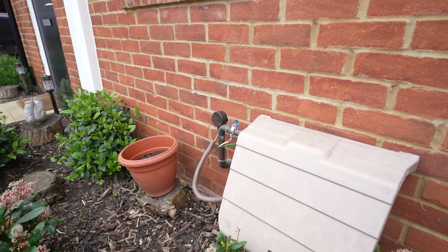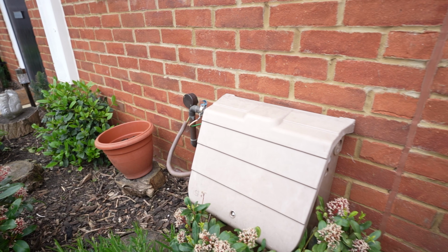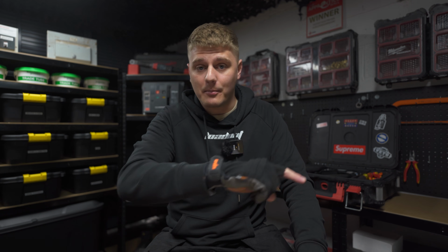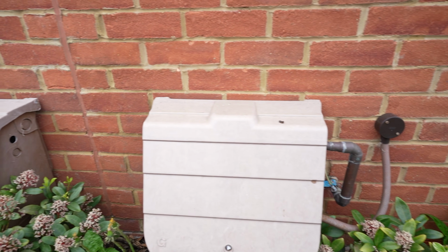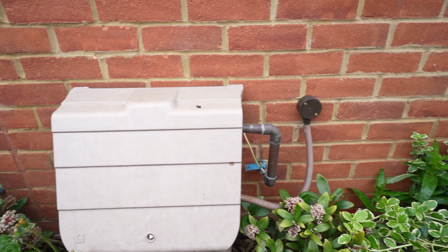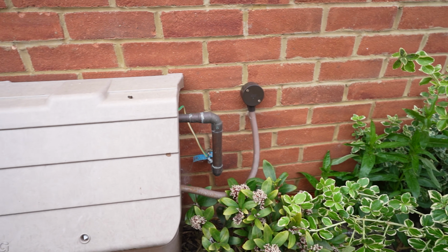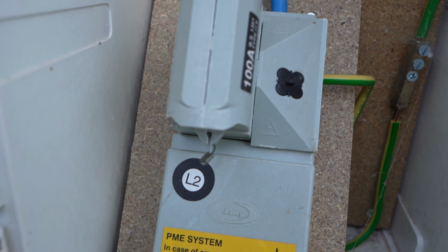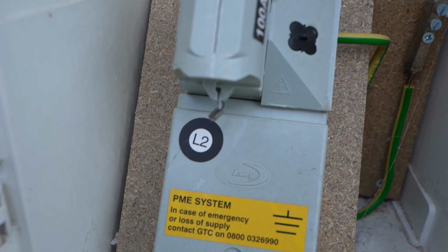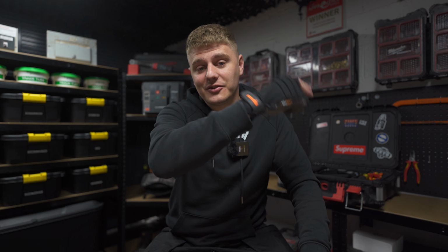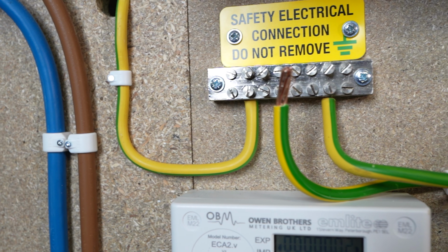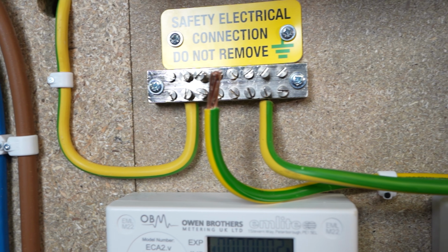Imagine next door's lost their neutral conductor, their PEN conductor. Their neutral current is flowing through their bond, through their pipe, which then runs next to your pipe. So then it goes onto that, comes up your main equipotential bond into your system, and then is using your PEN to get back to the supply transformer. Now, when you isolate your installation, the neutral current of next door is going to have nowhere to flow. It's obviously going to be sitting on all of the exposed and extraneous conductive parts, the MET and stuff like that. Obviously, that can be extremely dangerous. The current there and the potential difference, you're going to get hurt.